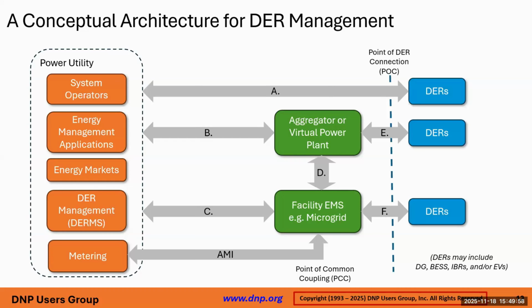Utilities typically use 2030.5 or DNP for this communication, while coordination of individual resources happens over whatever protocols those subsystems support. One place EPRI has seen IEEE 2030.5 adopted is for small-scale DERs, where utilities want to use the internet for connectivity—2030.5 provides end-to-end security, which Robby will talk about later, and is well-suited for internet-based communications. In contrast, DNP tends to be more prevalent with larger-scale systems, especially under today's telemetry-based requirements.